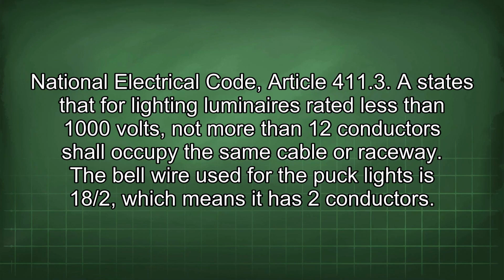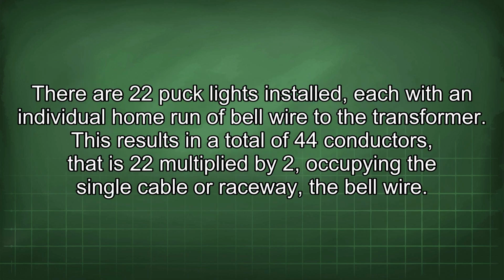National Electrical Code, Article 411.3, states that for lighting luminaires rated less than 1000 volts, not more than 12 conductors shall occupy the same cable or raceway. The bell wire used for the puck lights is 18/2, which means it has 2 conductors. There are 22 puck lights installed, each with an individual home run of bell wire to the transformer.